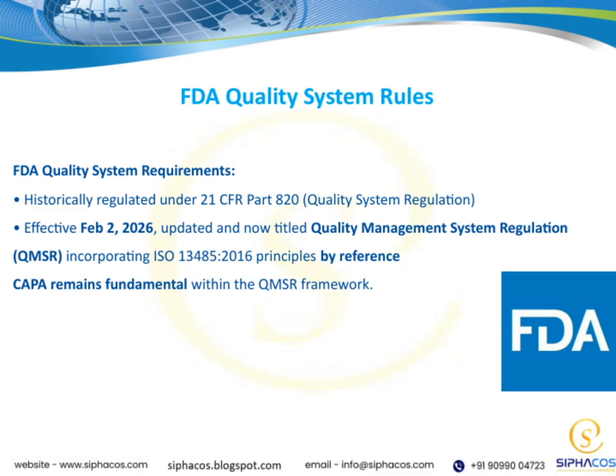This new regulation will incorporate principles from ISO 13485-2016 by reference, aligning FDA requirements more closely with international standards. One key point to highlight is that CAPA, which stands for Corrective and Preventive Actions, remains a fundamental component within this new QMSR framework. It underscores how vital it is to have a robust process for identifying and addressing issues to maintain quality and compliance.